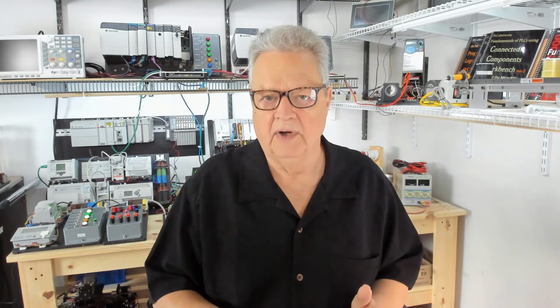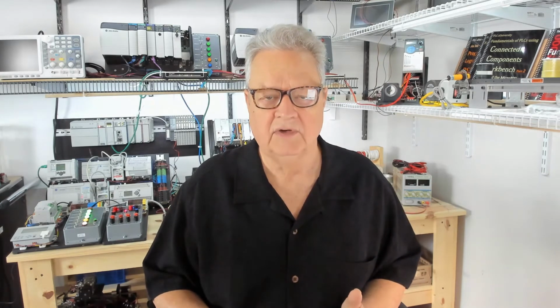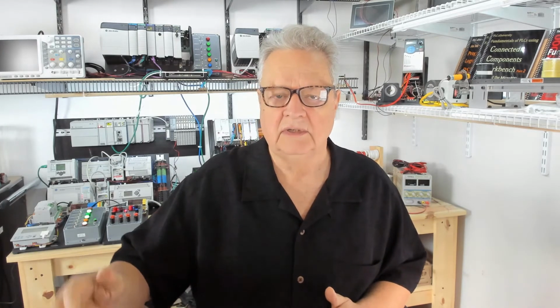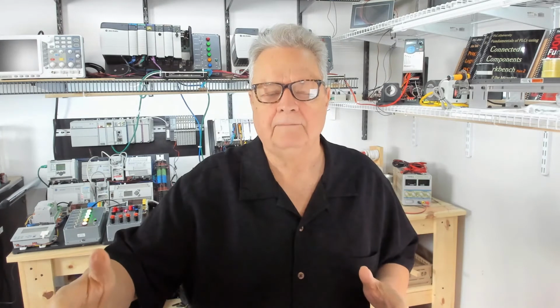Because you inserted a part in there, it now moves a 1 into the second least significant bit, and loads a 0 back into the least significant bit. And as you go around the table, every time an operation is completed at a workstation, then a bit is inserted into that position. So as the part moves through the different stations, the bit shift instructions shift the state of that part through those stations. That was a real crude explanation.